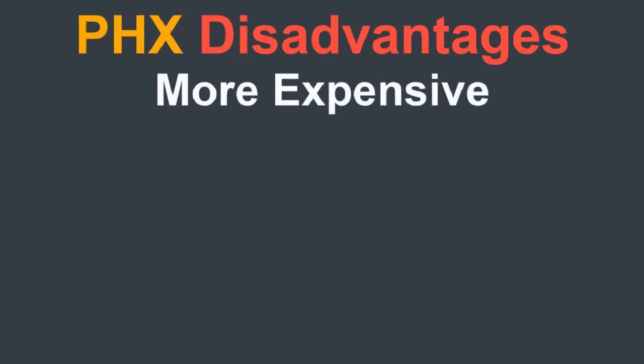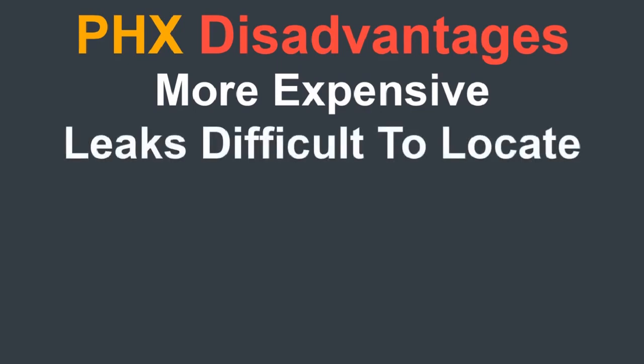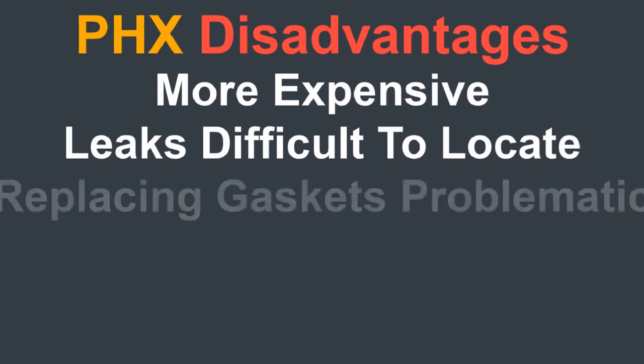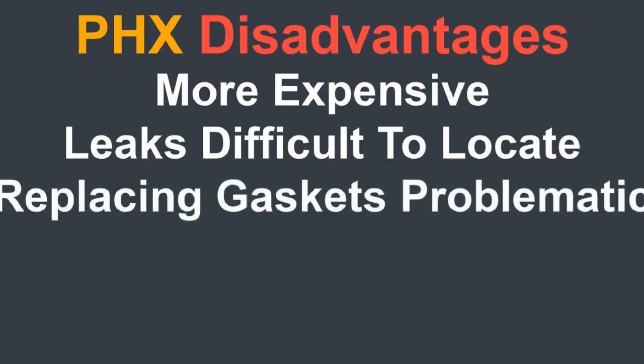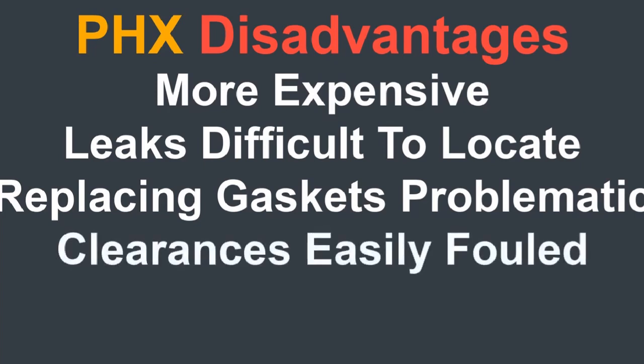If there is a leaking gasket causing one flowing medium to mix with the other, the leaking plate is often difficult to locate. Replacement of plate gaskets in situ can be difficult or impossible. Some plate gaskets must be returned to the manufacturer for replacement, which costs both time and money. When plates are compressed together to form a plate stack, the clearances between the plates are small. This increases the likelihood of fouling with a corresponding reduction in the heat transfer rate.